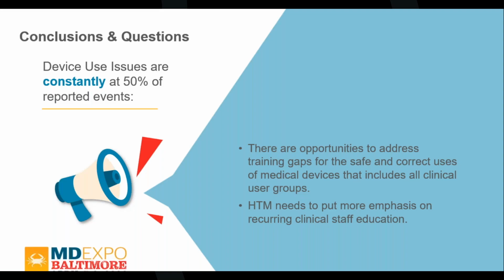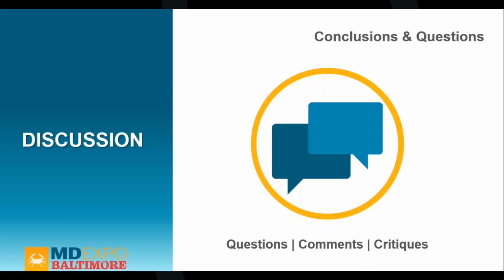Now, typically with consumable recalls, like your tubing sets and things, you're going to pull it off the shelf and send it back to where you got it from. That's the FDA recall definition for that. However, that's a remove from use recall. When it comes to our pumps, our anesthesia machines, our beds, whatever, those recalls are often corrective action recalls, and very rarely do the instructions for those recalls call for removing the device from use. You leave it in place until you can apply the correction in a timely manner, and then it's fixed essentially.